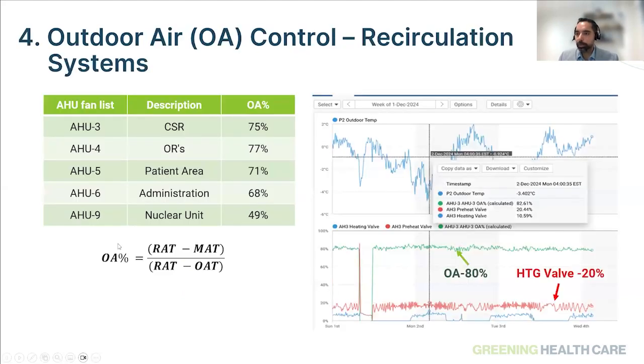In lieu of the time, I'm going to continue with the measure description. Outdoor air control: again, we looked at many facilities around how much outside air each facility is bringing in when the heating is on. In the graph on the right hand side, the green trend is your outside air percentage, and the blue and red trends on the bottom graph are your heating and preheat valves. You can see that both the preheat and the heating valves are on. The outside air is supposed to be around 33% as per the CSA, but they're bringing in 80%. Similar trends were seen for other systems as well.